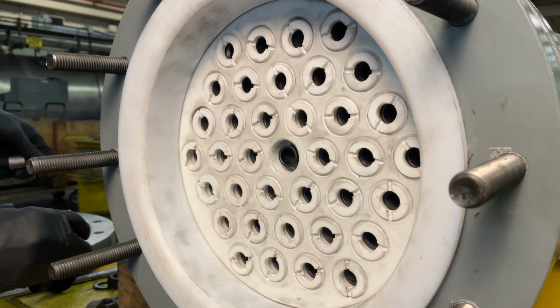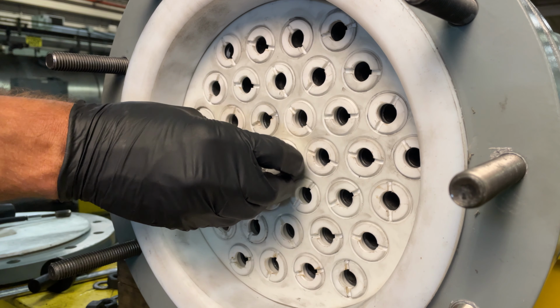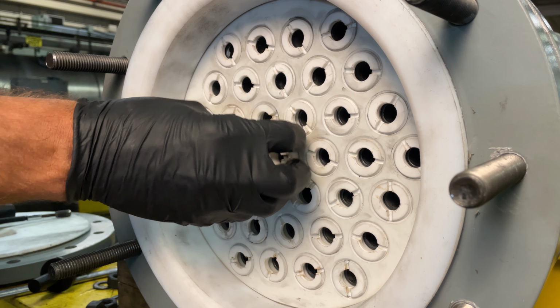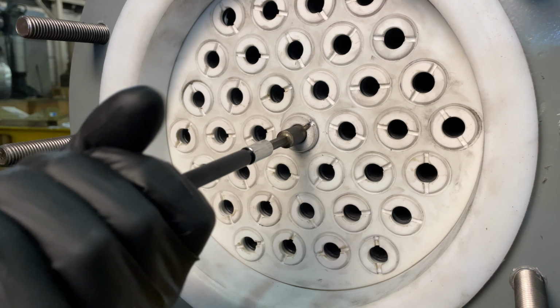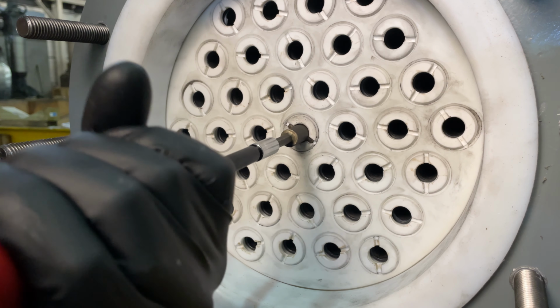Insert the tube nut by hand initially to avoid cross-threading and any damage to the threads on the tube sheet. I will then take the tube nut and torque screwdriver, just as I did on the other side, and reapply it to the tube sheet.